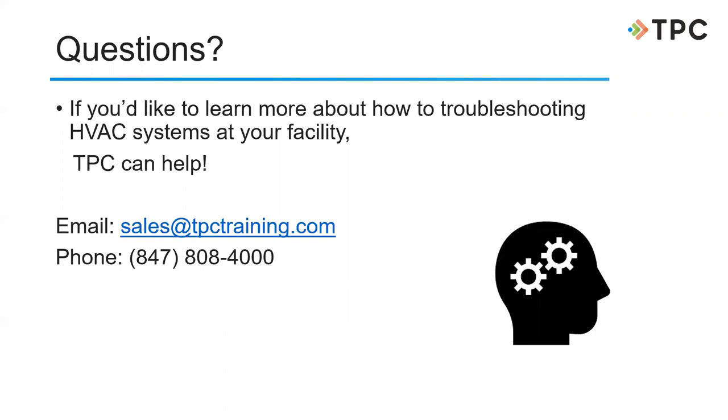Okay. And are there issues around, and maybe you could explain a little bit about, if we had an oversized condenser and what that could possibly mean if it was too large? Oversized condenser, that used to be that when it was a one-ton system, it was one size, and a two-ton was another size. Actually, oversized condensers nowadays are for high efficiency, the more heat you can get out. And sometimes they oversize condensers because you're going to have low ambient conditions, and you're going to have too much liquid in your system. So we use the condenser to allow it to hold extra liquid in your system. It's called flooding a condenser.